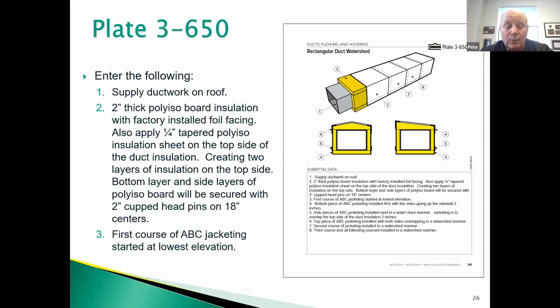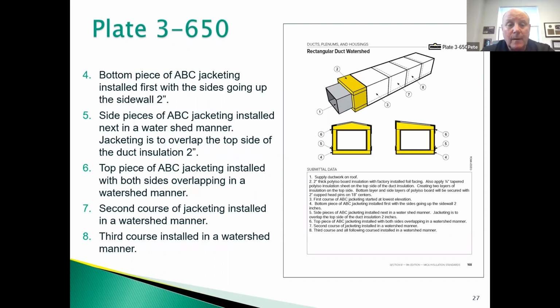Number 3: the first course of ABC jacketing starting at the lowest elevation. Number 4: the bottom piece of ABC jacketing installed first with the sides going up the sidewalls, describing how I'm installing the jacketing in a watershed manner. Number 5: the side pieces of ABC jacketing installed next in a watershed manner, overlapping the top side of the duct insulation by 2 inches. Number 6: the top piece of ABC jacketing installed with both sides overlapping in a watershed manner. Number 7: the second course of jacketing installed in a watershed manner. Number 8: the third course installed in a watershed manner.